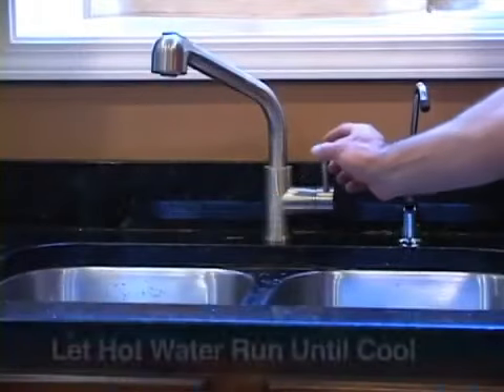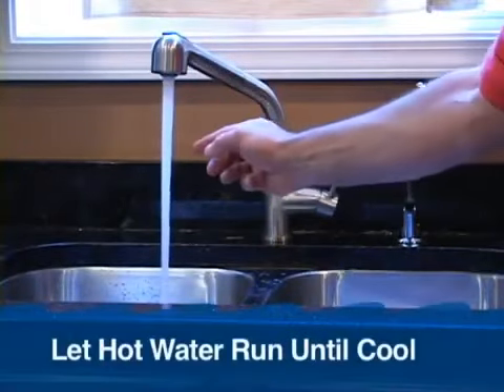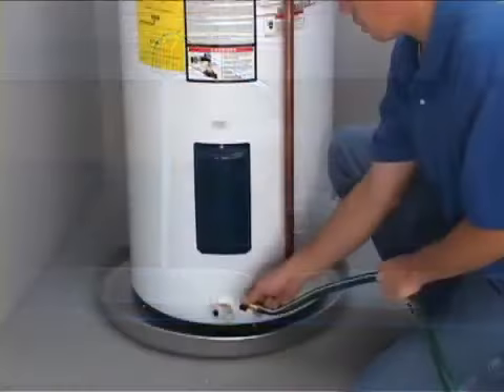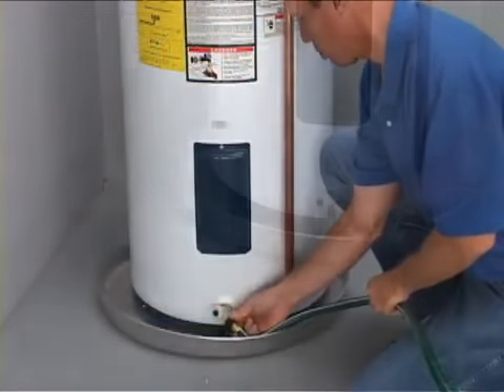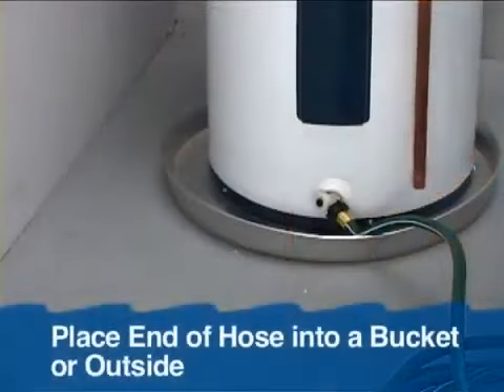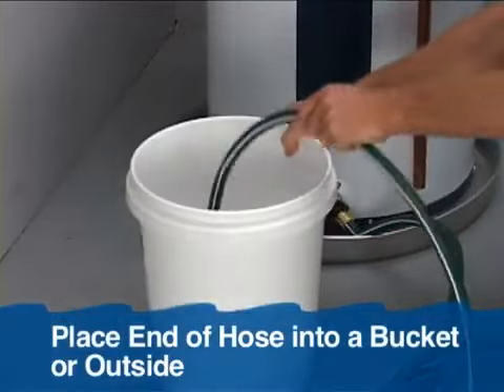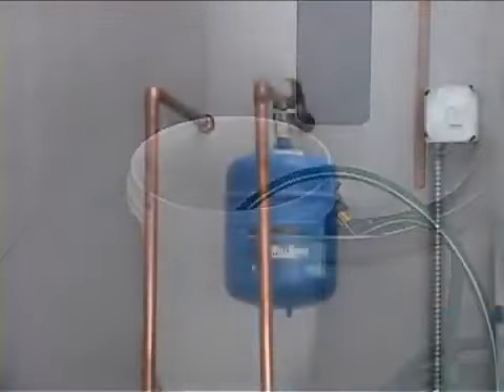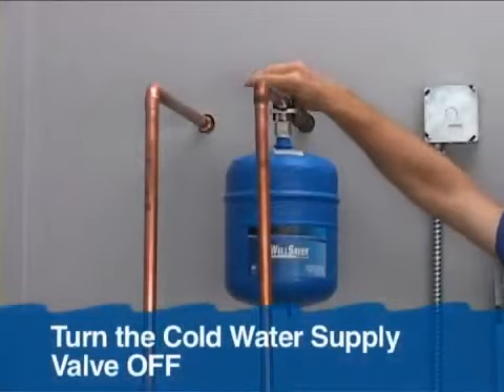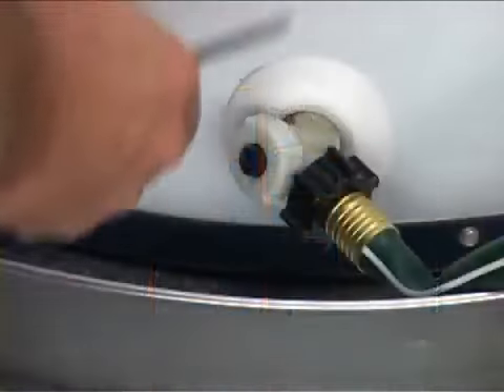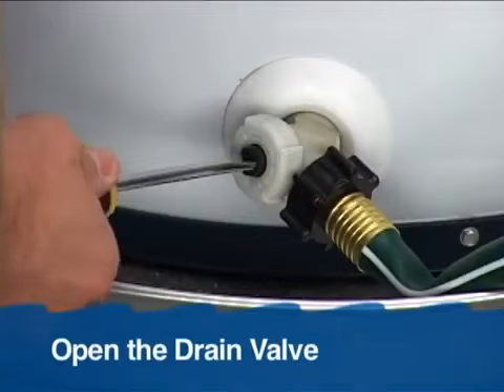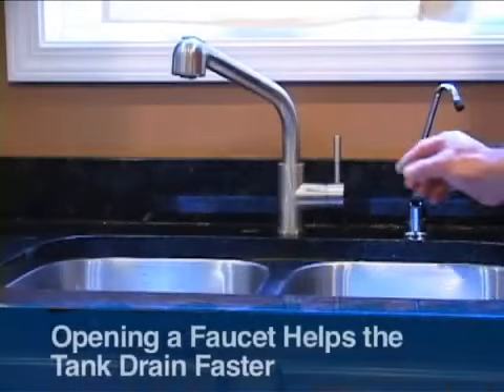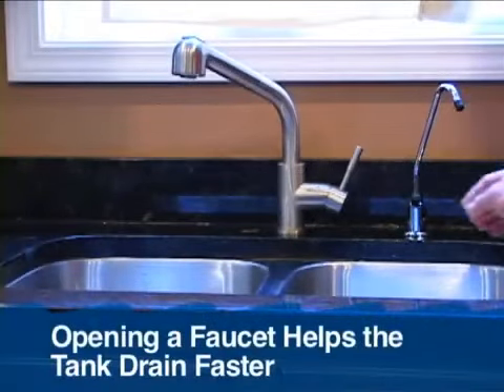Open a hot water faucet and let the hot water run until it's cool. Attach a garden hose to the drain valve. Place the other end of the hose in a drain or outside. You could also drain the water into buckets. Turn the cold water supply valve off and open the drain valve. Opening a hot water faucet will help the tank drain faster.